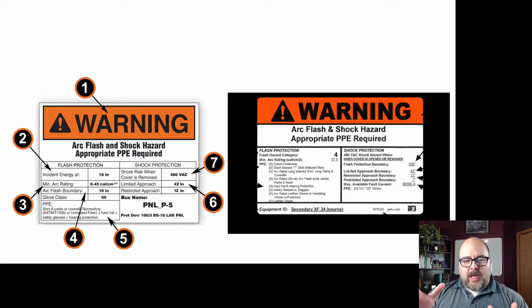Whenever you go up to an energy cabinet, a circuit breaker panel, whatever, you should see a warning label such as this. If you're ever on campus, you'll see these in the hallway. Certified electricians have completed these labels. It indicates, based on the amount of voltage and the design of the cabinet itself, the minimum arc ratings, the arc flash boundary, the type of glove required, the incident energy, the shock risk—basically information about the cabinet and what would happen should it become an arc flash site.